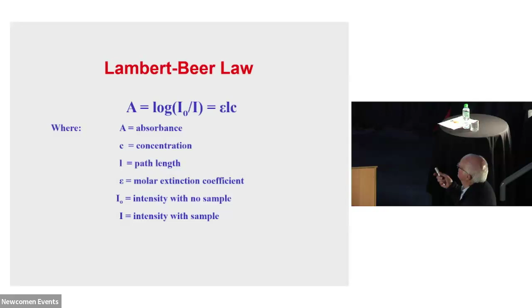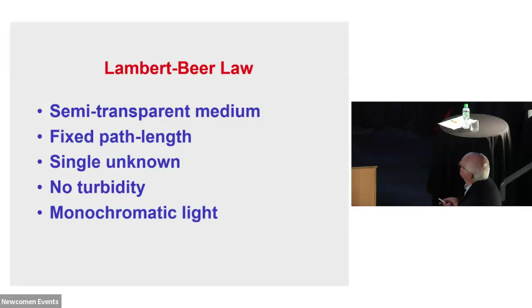The trouble is that the Lambert-Beer law works very well for semi-transparent mediums, and a finger ain't semi-transparent. It assumes a fixed path length, which it isn't because it's throbbing, a single unknown, well, there are multiple unknowns, no turbidity and monochromatic wavelengths of light. Unfortunately, fingers are turbid, so you never knew what was coming through, or whether the entirety of the light was coming through or not.